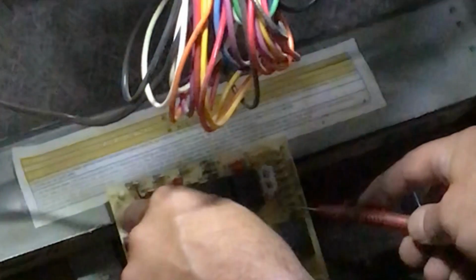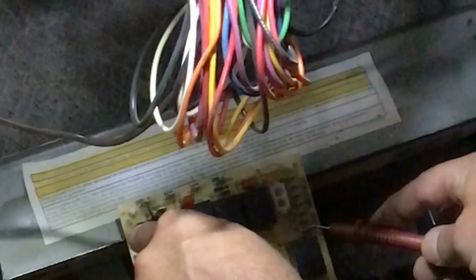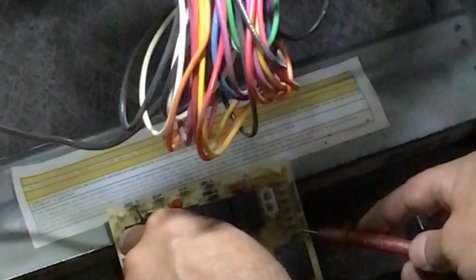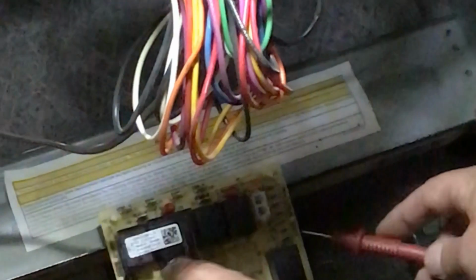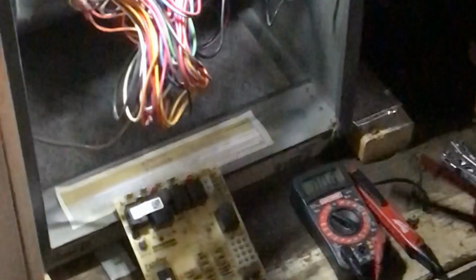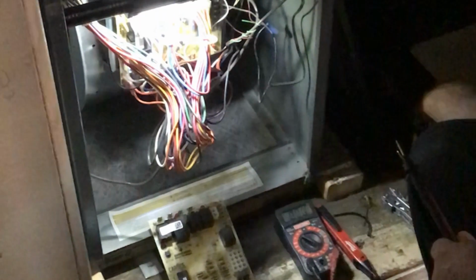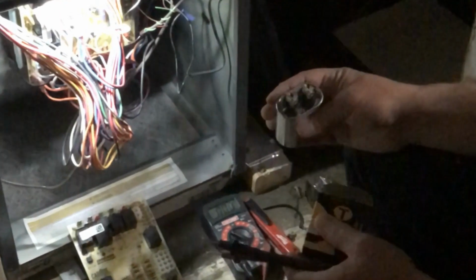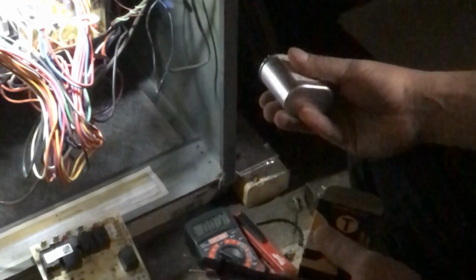If you do not have 120 volts coming out of the board to the fan, then your circuit board's bad, and that's why your fan isn't operating. If you do have the 120 volts, the next thing I would personally do is try to change out your capacitor, and it only takes a minute. Like I said earlier, they're cheap, and if you're wrong and you have to replace the fan motor, you're going to have to replace the capacitor anyway.